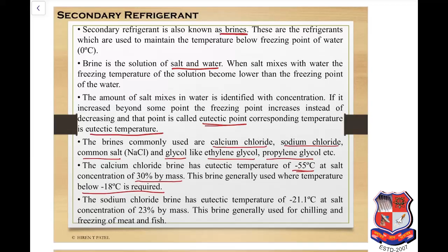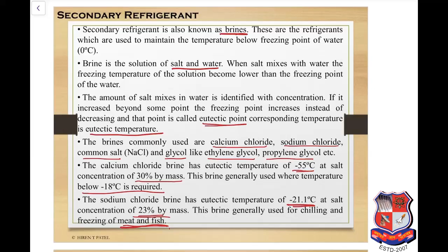In glycol, ethylene glycol and propylene glycol are used. The calcium chloride brine has a eutectic temperature of minus 55 degrees Celsius and salt concentration of 30% by mass. This brine is generally used where temperature below minus 18 degrees Celsius is required. The sodium chloride brine has a eutectic temperature of minus 21 degrees Celsius at the salt concentration of 23% by mass, and this brine is generally used for chilling and freezing of meat and fish. Normally this brine is used in ships when fishermen are required to store the meat and fish.